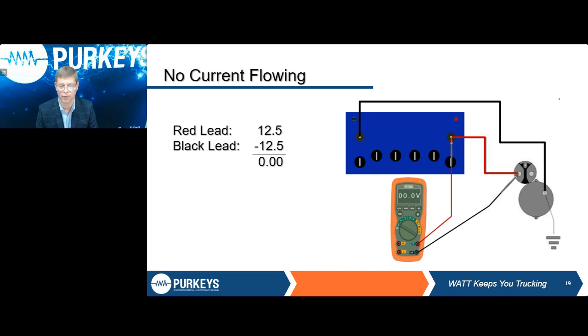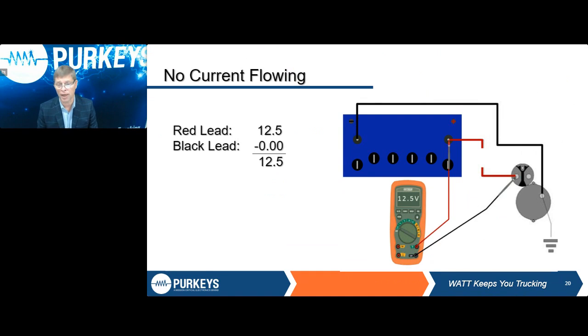Now, if you had your meter hooked up like this and your meter did display 12.5, what should that immediately tell you? And the answer is there's a break in that wire. Now, generally this won't ever happen with big starter cables. Generally a big 1/aught, 2/aught cable doesn't break. But these same rules apply to any circuit on that truck. And we've done this on boards before, and people will skip right over because their first reaction is, ooh, 12.5, that's a good reading, and they skip right over. If you're paying attention, that's when the bells should be ringing and lights going off saying, hey, here's my problem. I got a break between here and here. Now, that could be a break in the wire.